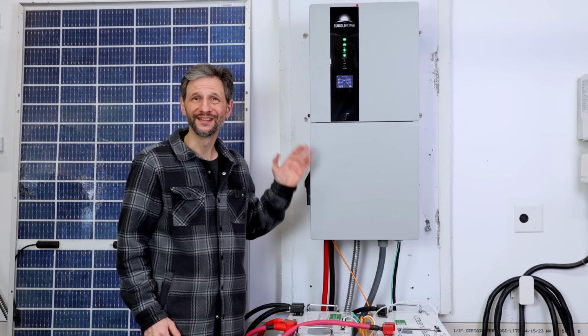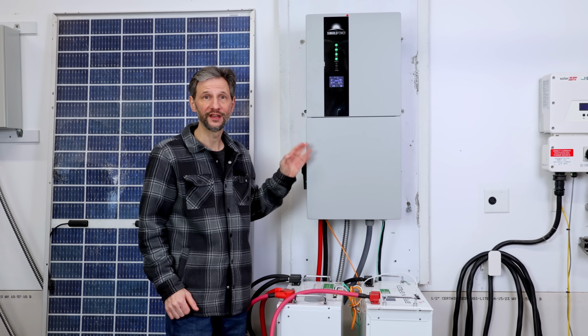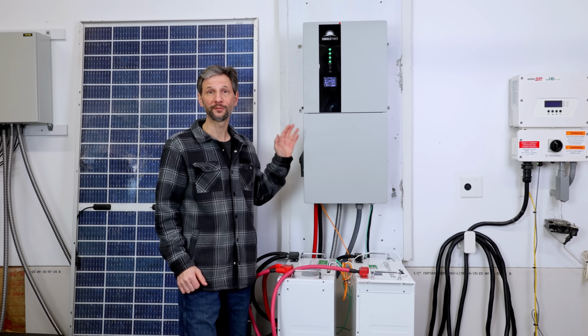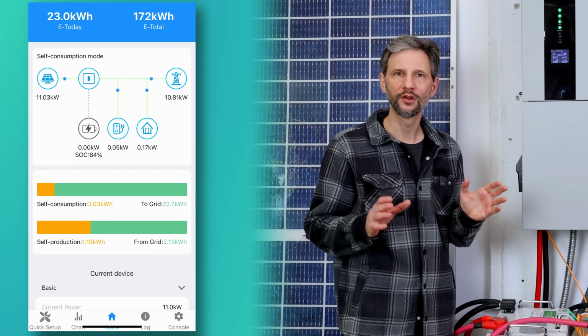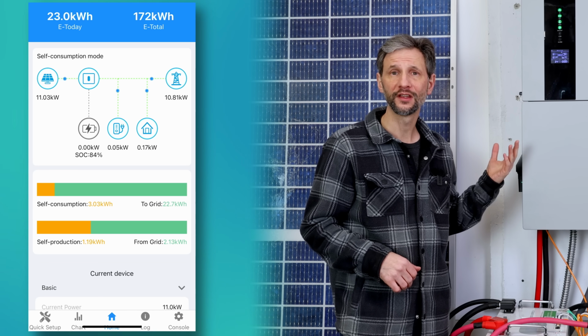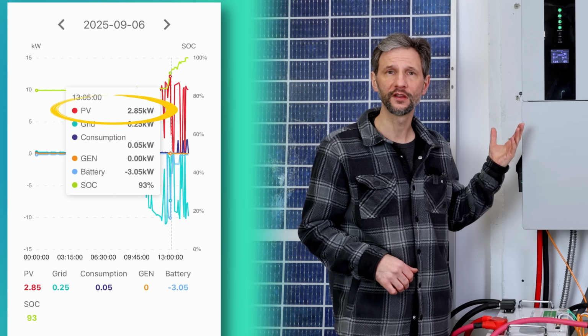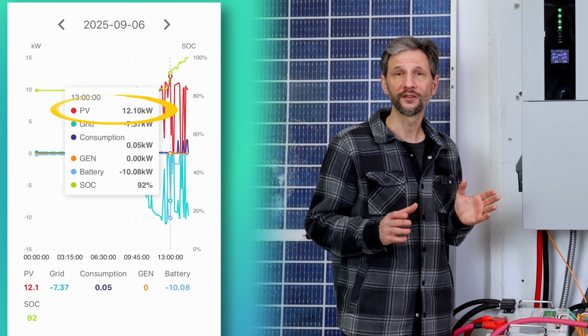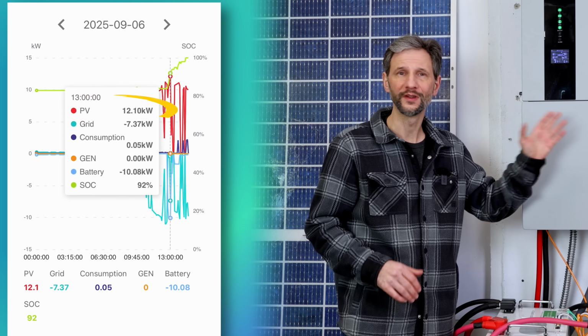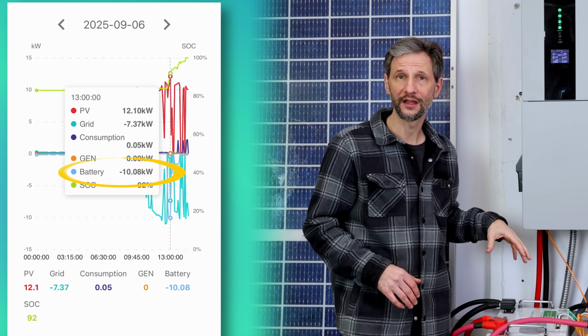It would have been significant effort to reconfigure my array to confirm the 15 kilowatt max PV input, but I was able to run steadily in the 10 to 11 kilowatt range, and I hit a peak over 12 kilowatts. The inverter can only convert 11.4 kilowatts, so anything beyond that has to go into the batteries anyway.